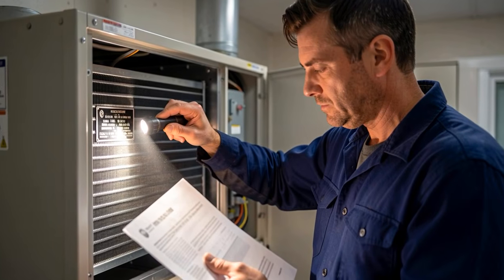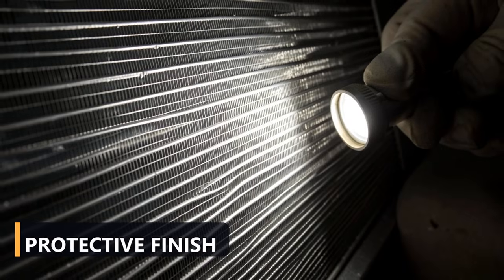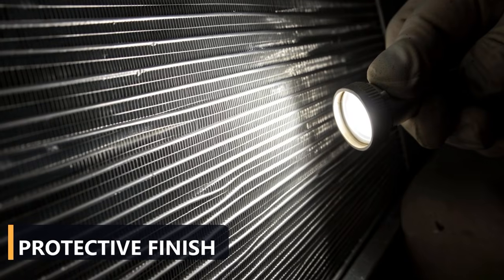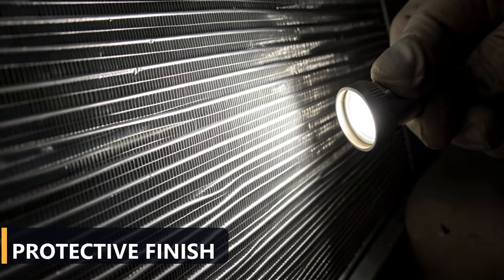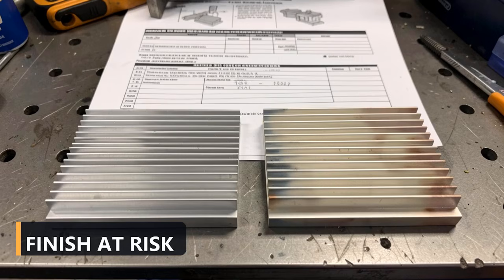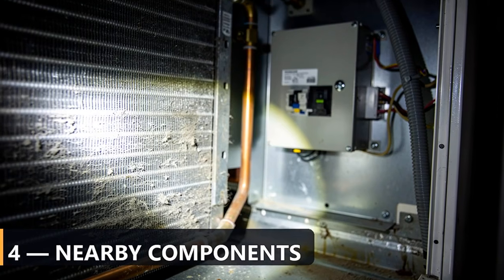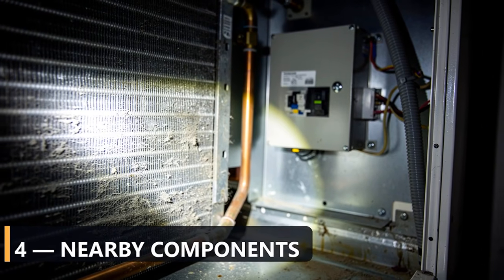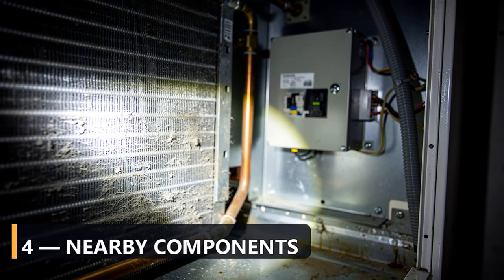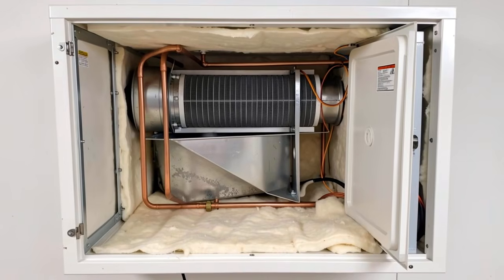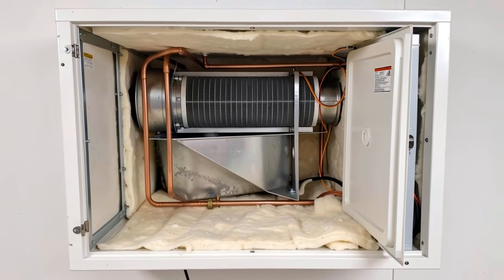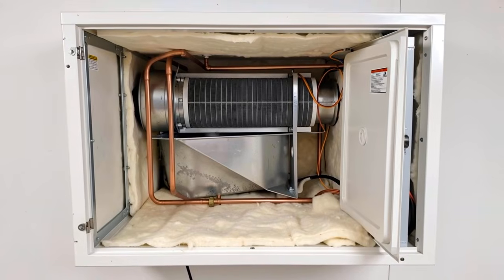Their existence does not prove that an unlabeled brown bottle from the medicine cabinet is an equivalent substitute. This is why an experienced technician checks the model, coil material, coating, product label, and rinse instructions before applying anything. If a coil has a special protective finish, using an unapproved chemical may discolor it, reduce protection, or complicate a warranty claim. The hidden cost is not always an immediate hole in the metal. It may be a surface that begins collecting dirt faster or deteriorating sooner.